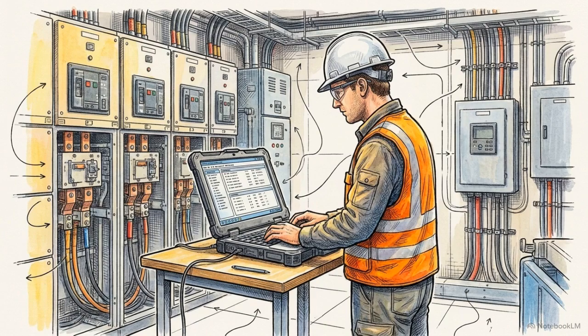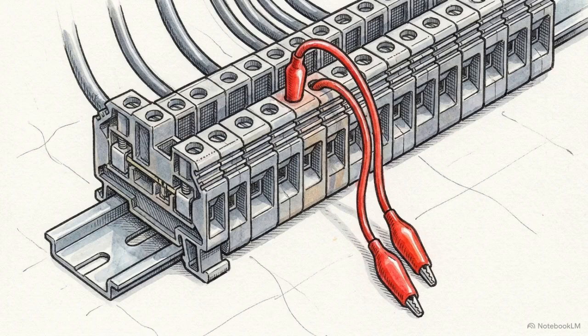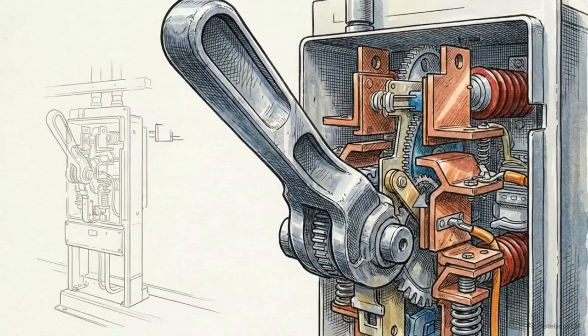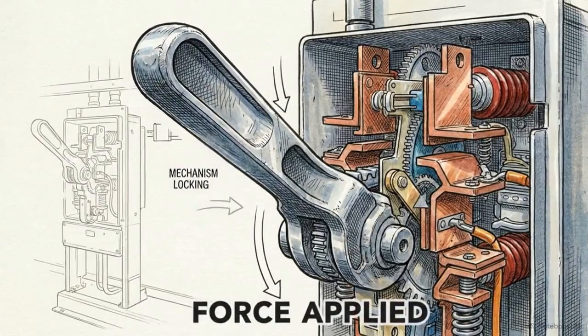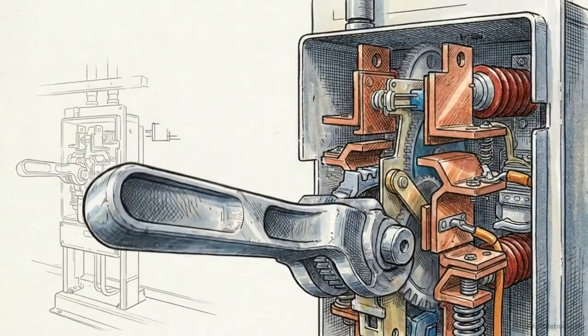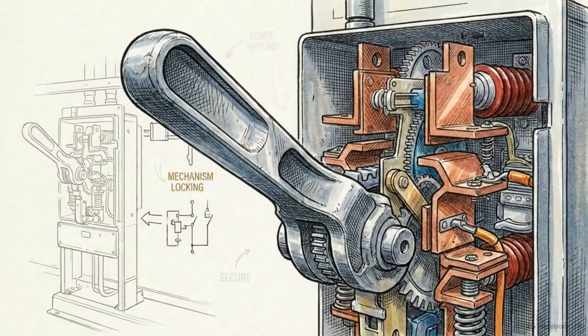The final requirement before releasing a bay is equipment normalization. Leaving a single temporary test link or bypass in place compromises the active grid. Normalization requires removing all test leads, restoring earthing to approved switching states, and reinstalling all panel covers and physical barriers.